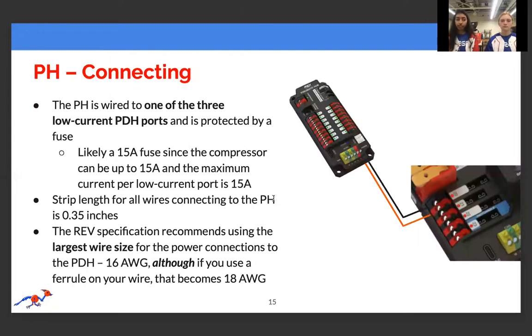To connect, the PH is wired to one of the 3 low current PDH ports and is protected by a fuse, most likely a 15 amp fuse, since the compressor can be up to 15 amps and the maximum current per low current port is also 15 amps. Strip length for all wires to the PH is 0.35 inches, and the REV specification recommends using the largest wire size for the power connections to the PDH, which would be 16 gauge. But if you use a ferrule on your wire, that becomes an 18 gauge wire.